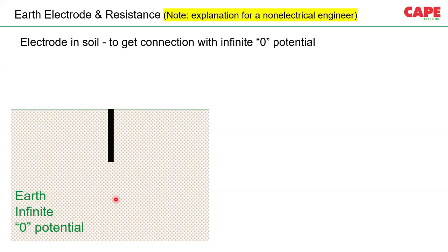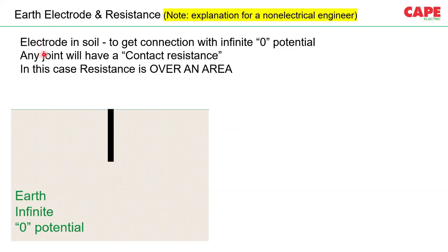For this purpose, we put an earth electrode in soil because we are in a TT network. So the current has to go back to the source through the earth electrode, through the soil, returning back through the earth electrode of the neutral of the transformer. As a result, your protective device is going to trip. Now, in order to create a connection with this infinite earth, which is at zero potential, we put an earth electrode in soil, because the earth has a certain resistivity. It is not zero. It has certain resistivity depending upon the soil, probably from sometimes 10 ohm to sometimes several thousands.